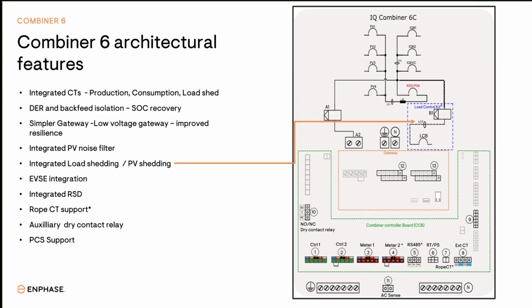Potentially heavy loads that can impact microgrid health during a power outage can be rerouted to this circuit. Integration of current and future generations of Enphase IQ EV chargers into the Combiner 6C allows for relocating heavy EV charger loads out of the main electrical panel. Enphase EV chargers can be dynamically controlled to optimize for efficient energy usage. The PV/RSD or aggregate PV circuit breaker is a feature in the system that provides a single-point, compliant means of PV system rapid shutdown and a valid form of energy storage system disconnect, all subject to local AHJ approval.